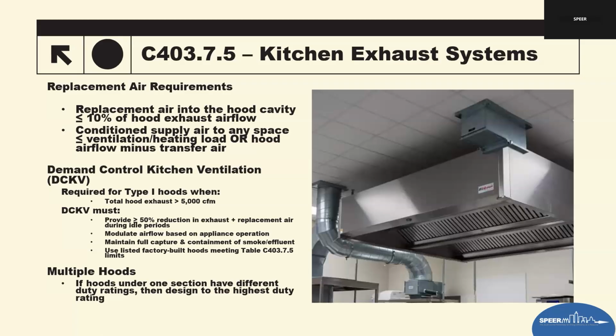Use hoods that are factory built and listed by a recognized testing lab. There are probably some out there that don't have those tested lab certificates. This basically prevents constant 100% airflow operation, which wastes a lot of energy, so just running them consistently. Multiple hood sections: when multiple appliances with different duty ratings share a single hood, the design must meet the highest duty rating. This ensures capture performance for the most demanding appliance that's there.